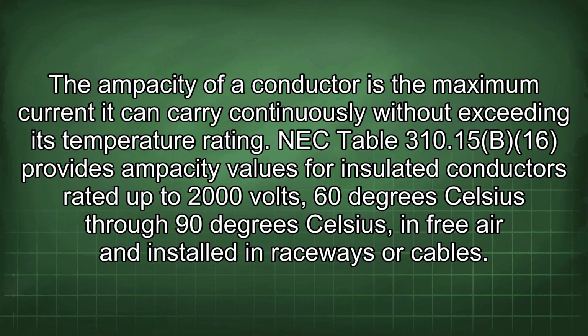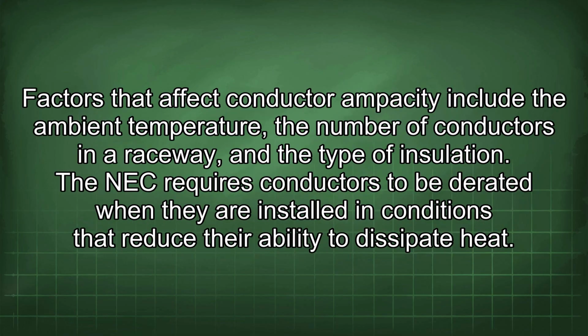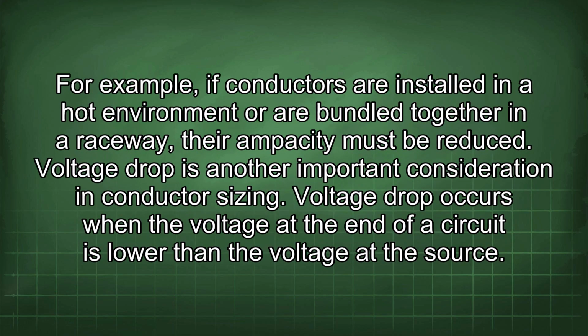NEC Table 310.15(B)(16) provides ampacity values for insulated conductors rated up to 2000 volts, 60 degrees Celsius through 90 degrees Celsius, in free air and installed in raceways or cables. Factors that affect conductor ampacity include the ambient temperature, the number of conductors in a raceway, and the type of insulation. The NEC requires conductors to be derated when they are installed in conditions that reduce their ability to dissipate heat. For example, if conductors are installed in a hot environment or are bundled together in a raceway, their ampacity must be reduced.